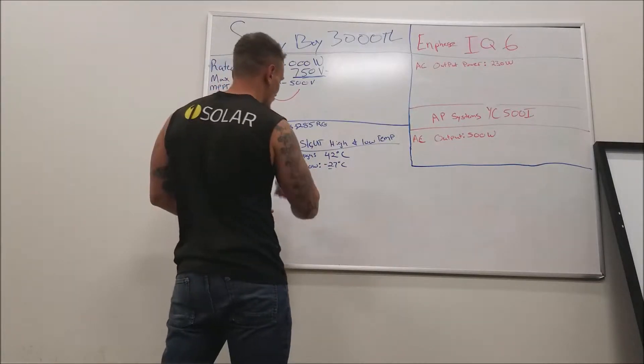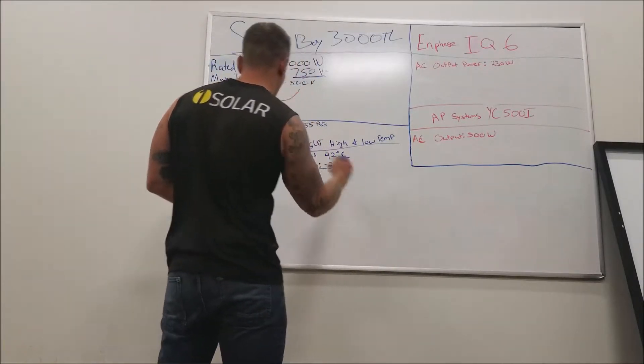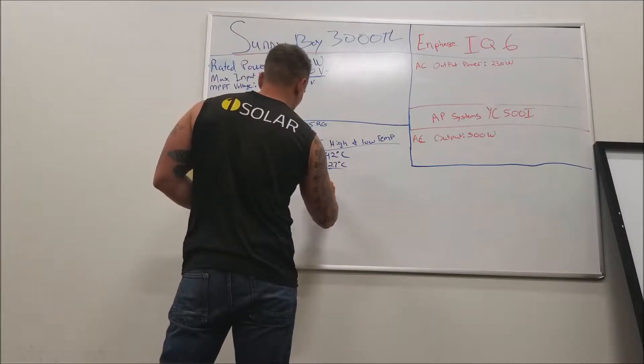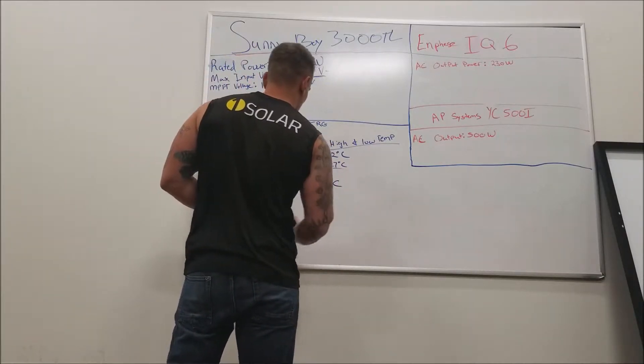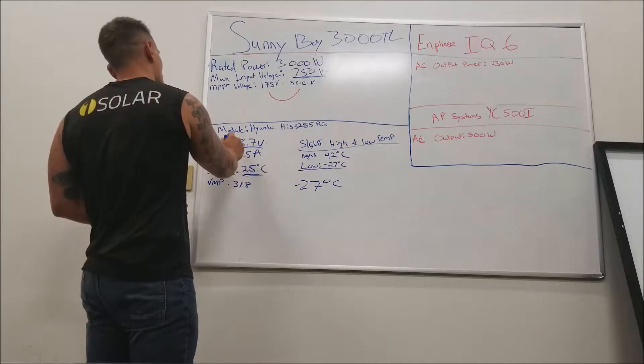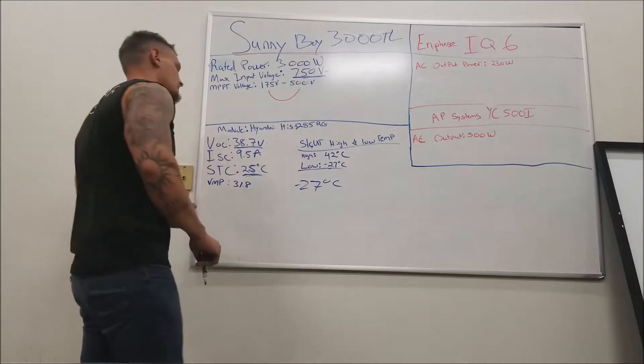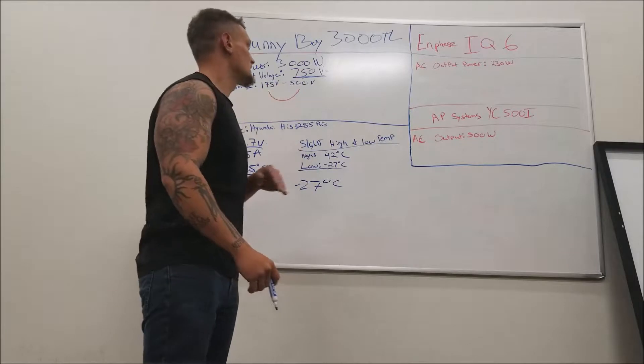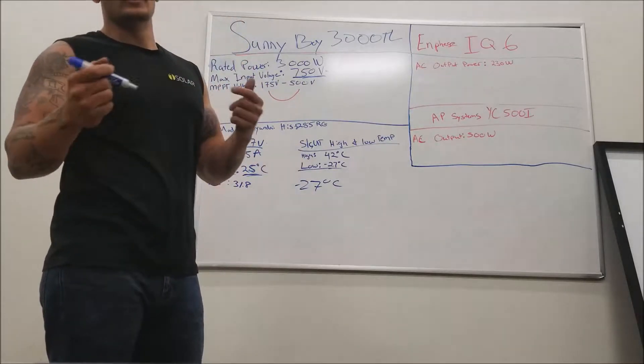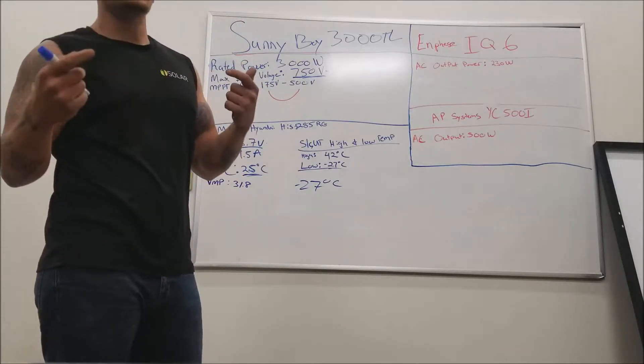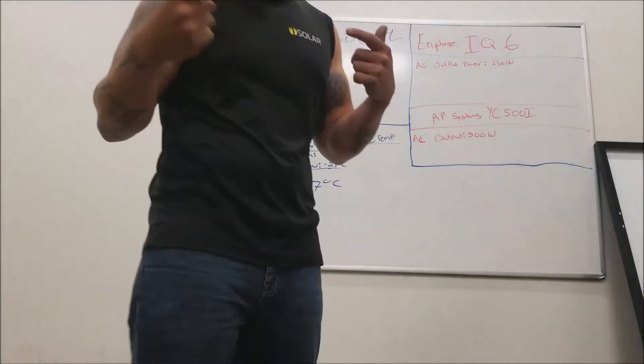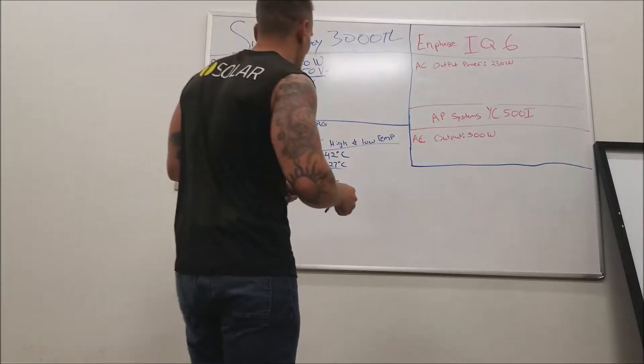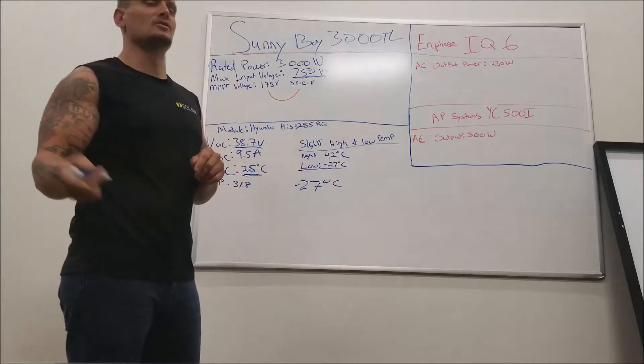We're in Utah, so our lowest temperature — which is going to increase our voltage — is negative 27 degrees Celsius. We want to see how that changes our VOC so we can figure out how many panels we can put in a string without exceeding 750 volts. We go to the NEC code book, 690.7A, which tells us what correction factors we need to use.